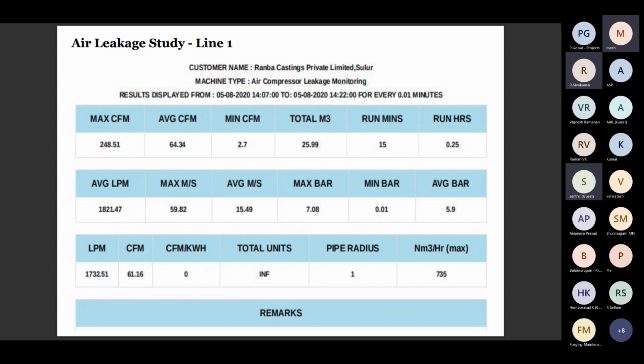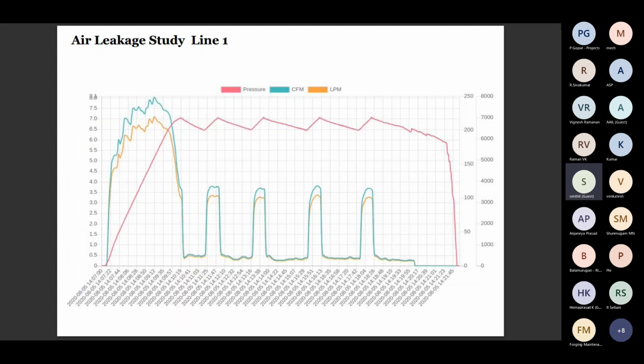Another alarming thing here is that the maximum air velocity in meters per second is very, very high because of improper sizing. The velocity should be a maximum of 15 meters per second. Below 15 means excellent, 15 to 30 means somewhat average, but the maximum here goes to 59.82. Next one. So this is the air leakage pattern, how much loss they have.